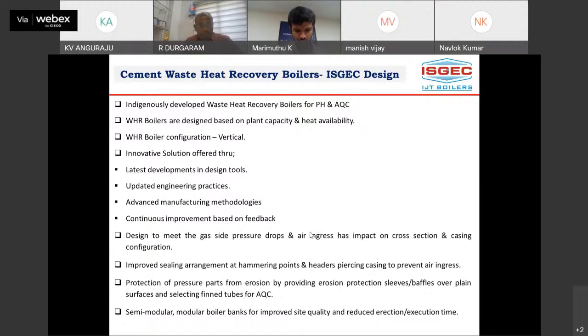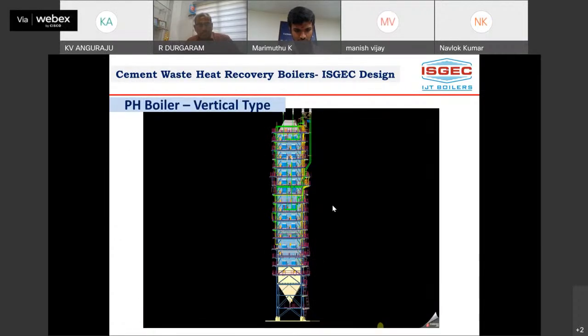Nowadays the project timing is very vital. People come with even 9 months, 10 months and so on, so definitely the erection time at site has to be reduced. So we design the boiler with both modular and semi-modular construction so that it can be erected quickly. In one of the projects, we supplied all the AQC modules like containers. You just stack one over the other, finish the seal welding of the casing, then the boiler is ready. This is such an arrangement.